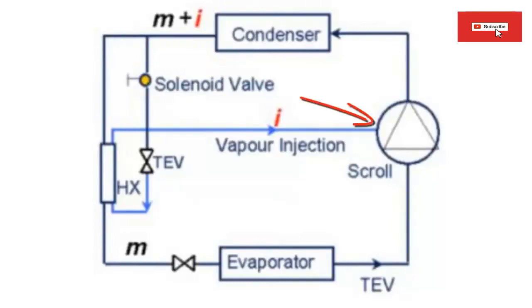17. The key point of the system is the saturation temperature of the refrigerant at the injection point. 18. This temperature is a function of the condensation and evaporation pressures, being the injection pressure value defined by the compressor manufacturer.